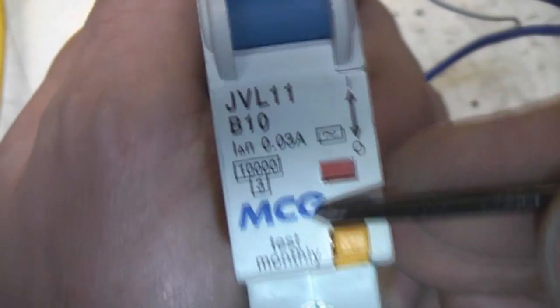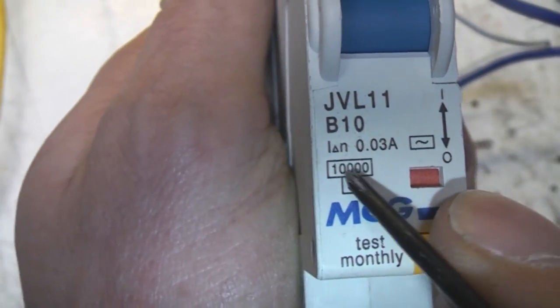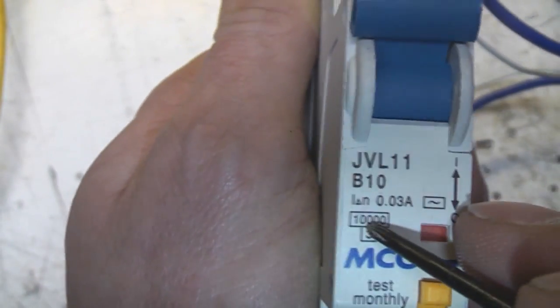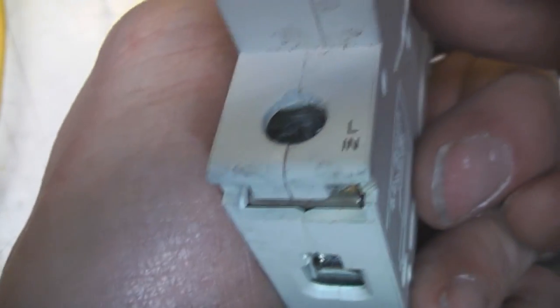There's a few other things on here. There's this 10,000. Now that's its peak current surge capability. So basically, if you have a really hefty incoming supply, obviously these things could be used on distribution boards fed from massive bus bars capable of huge amounts of current. So if there is a short circuit on the output, for a short amount of time a very high current can flow in between the time that current starts and this breaker actually trips out, because obviously it's a mechanical device, so it takes a finite amount of time for it to trip. So that's basically its maximum current rating to guarantee that this thing won't just catch fire or explode or generally cause mayhem.